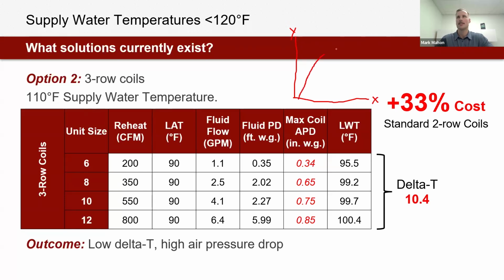What we kind of see is this shape of curve, and what I consider this top end to be, that's coil saturation. Eventually, we're adding more GPM through the unit, and we're not really getting any improvement in capacity at all. All we end up seeing is super high fluid pressure drops and big distribution pipes and a lot of first cost for really no benefit.